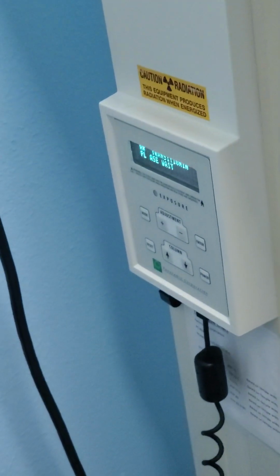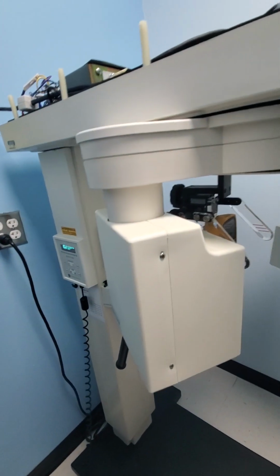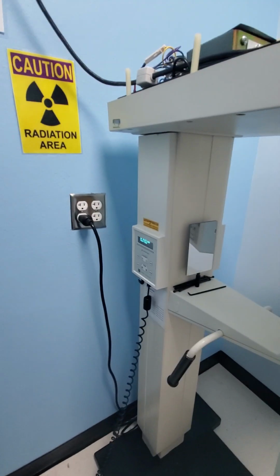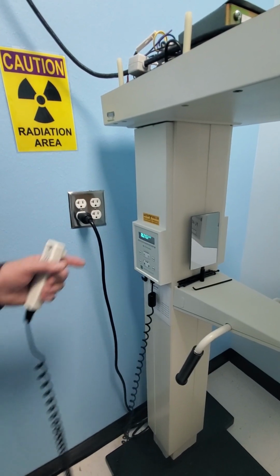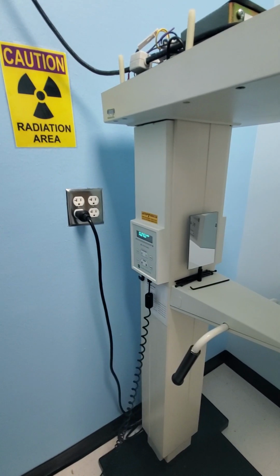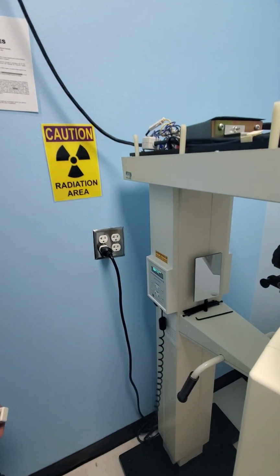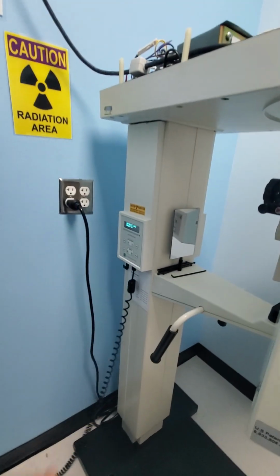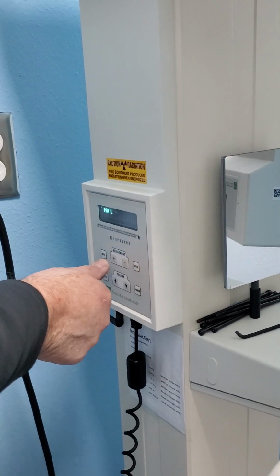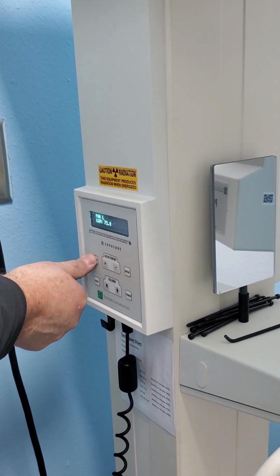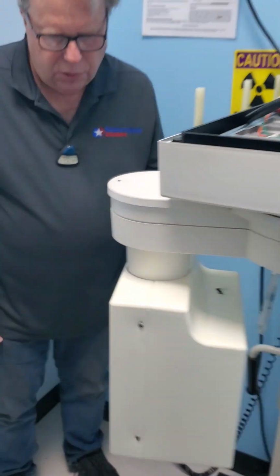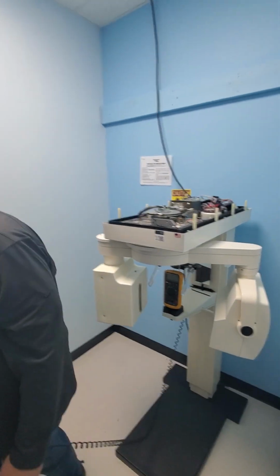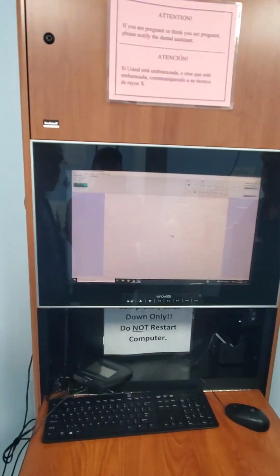So we're going back to left pan. We're setting up an exposure, and since the arm wasn't in position, we're moving it to the left-hand side. We do left side start because the control panel's on this side, no other reason than that. The control panel will mount on either side of this machine. So in some situations we mount it on the other side. So press mode. 75 is good for shooting a picture of my meter. Press mode again. We're ready for exposure. So this is DVM and panoramic. And you always look for a green light. You have to have a green light to shoot to acquire the image. When it starts to scan, it's going to change to yellow.